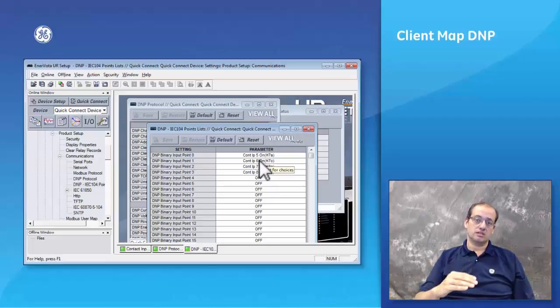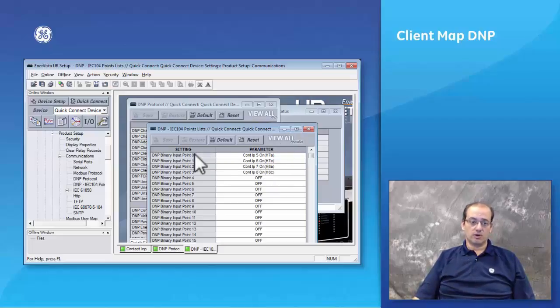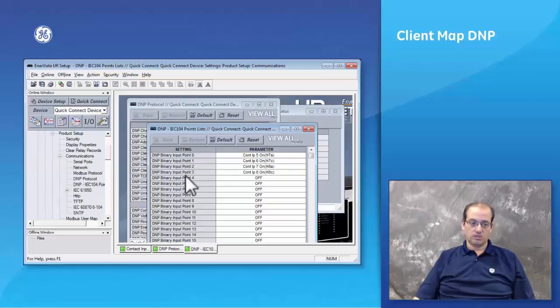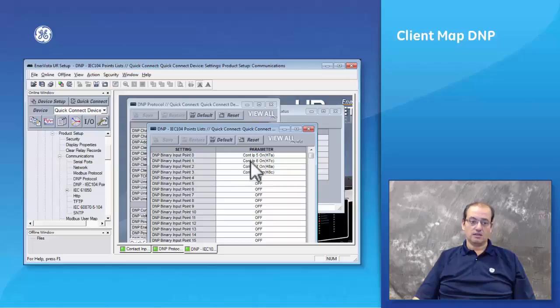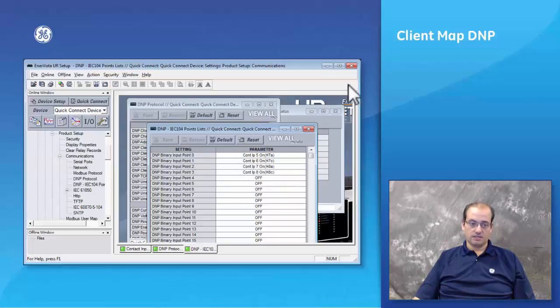Now this will translate to the D400 as point number zero, point number one, point number two, point number three. So the D400 will poll the UR relay for point number zero, one, two, three. The UR relay will send contact input number five, six, seven, and eight.